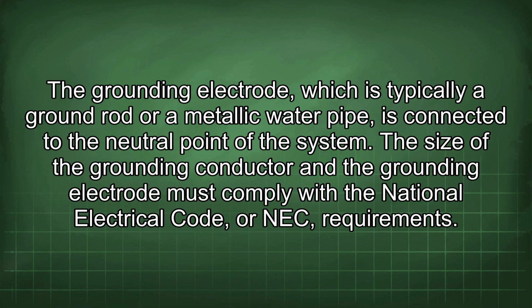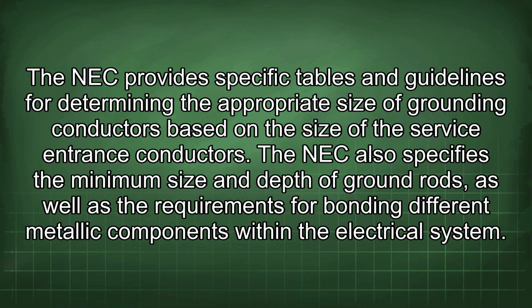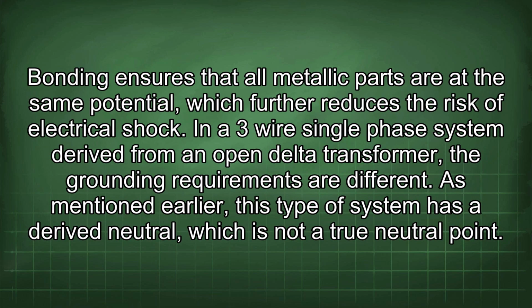The size of the grounding conductor and the grounding electrode must comply with the National Electrical Code, or NEC, requirements. The NEC provides specific tables and guidelines for determining the appropriate size of grounding conductors based on the size of the service entrance conductors. The NEC also specifies the minimum size and depth of ground rods, as well as the requirements for bonding different metallic components within the electrical system. Bonding ensures that all metallic parts are at the same potential, which further reduces the risk of electrical shock.